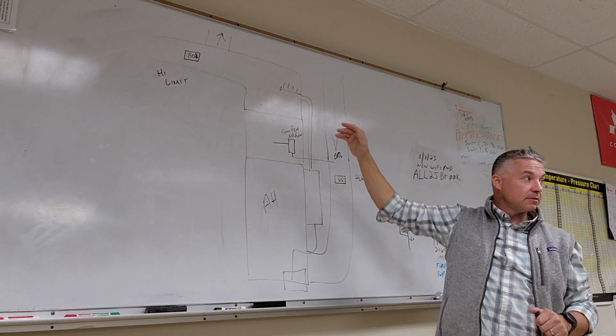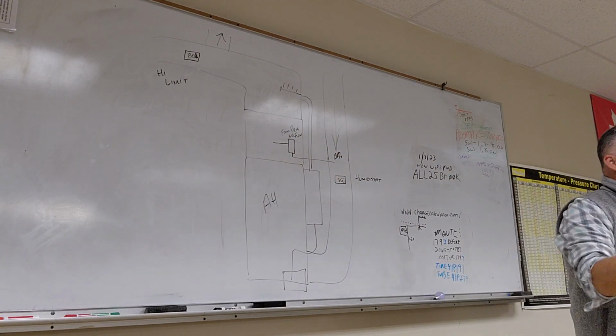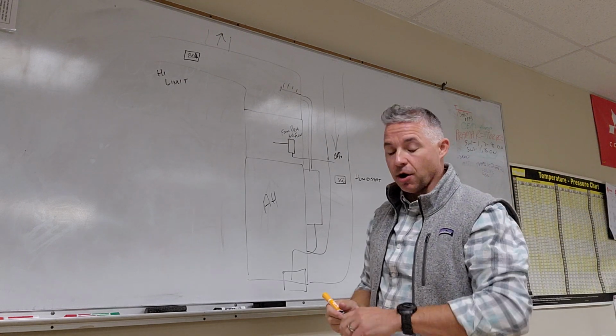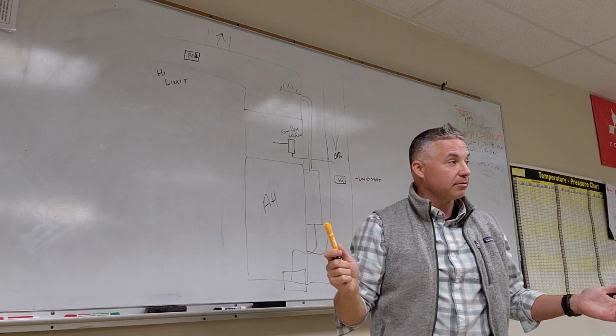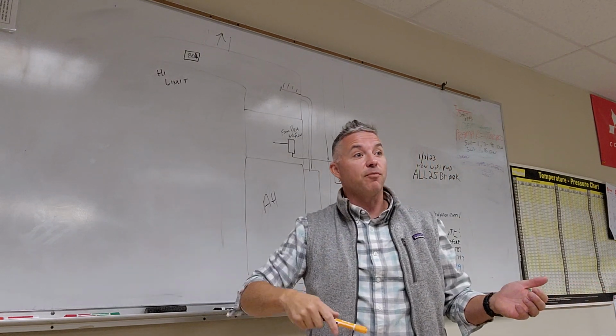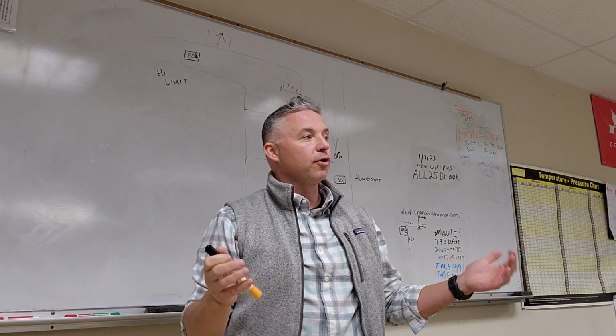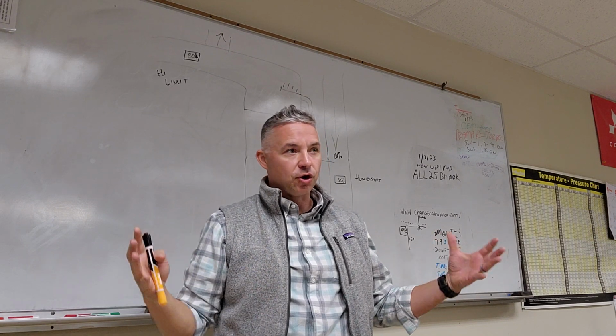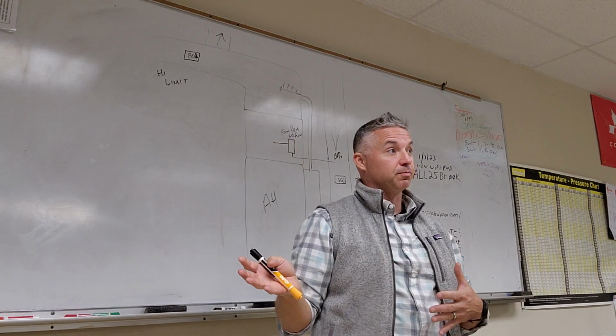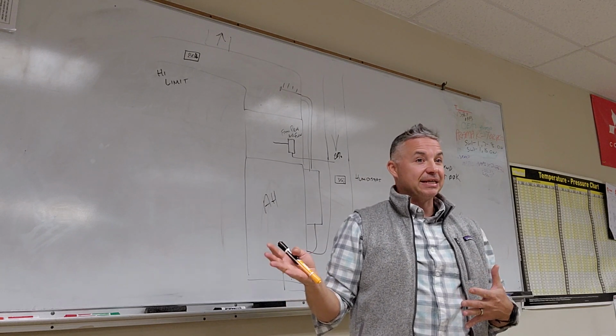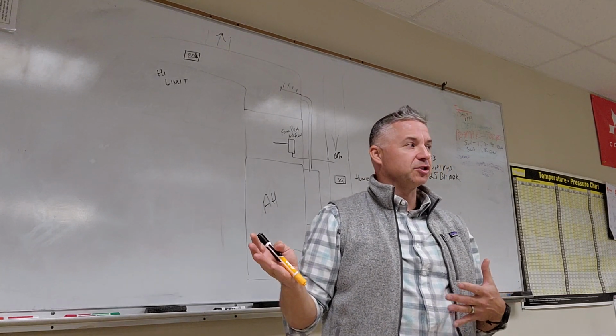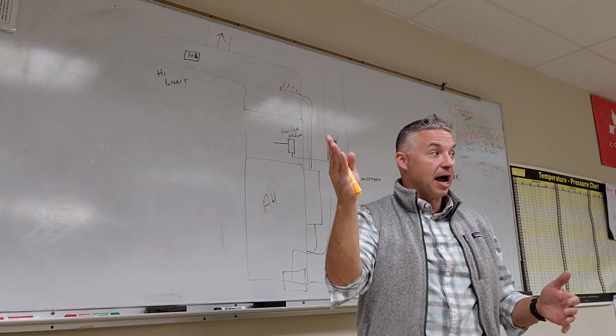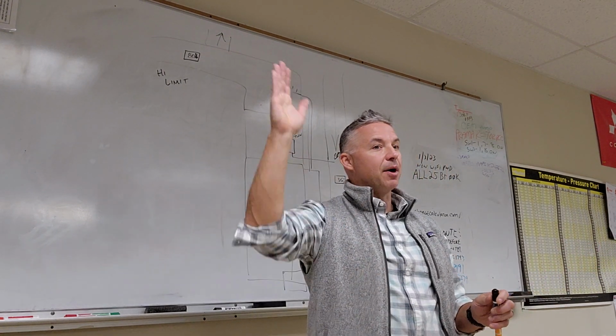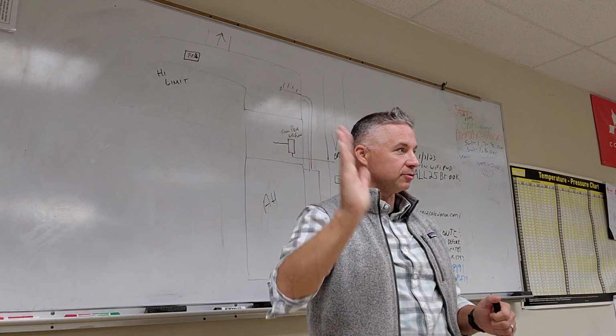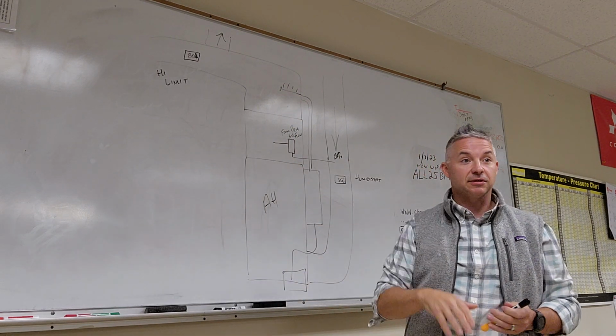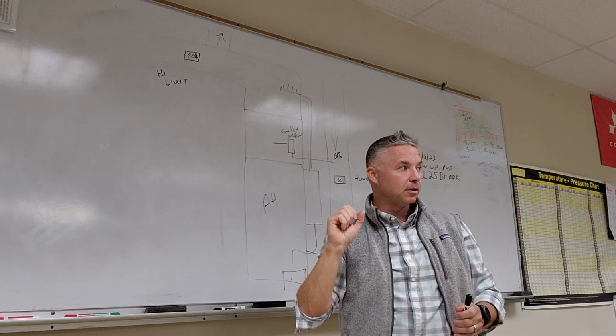fan proving, okay? Now with ECM motors coming out on the market and all these installs that we were doing, right? We started installing these things many years ago before variable speed, before ECM motors were invented and were the norm in our industry. Now they're the norm. Years ago it was, what were they called, Ryan? PSC motors? Permanent split capacitor motors? Single speed, right? On, off, on, off. There was no ramp up to a speed. There was no ramp down. On, it was off. That's when airflow switches work the best. Boom, boom, boom, boom. Okay?